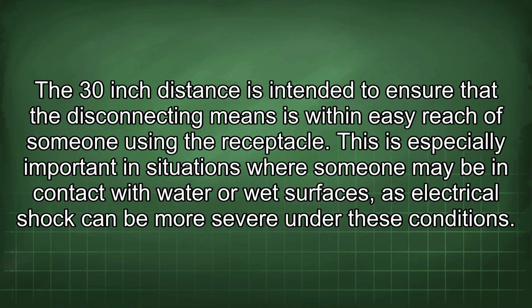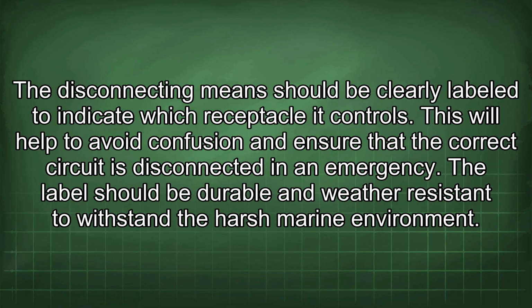This is especially important in situations where someone may be in contact with water or wet surfaces, as electrical shock can be more severe under these conditions. The disconnecting means should be clearly labeled to indicate which receptacle it controls. This will help to avoid confusion and ensure that the correct circuit is disconnected in an emergency. The label should be durable and weather resistant to withstand the harsh marine environment.